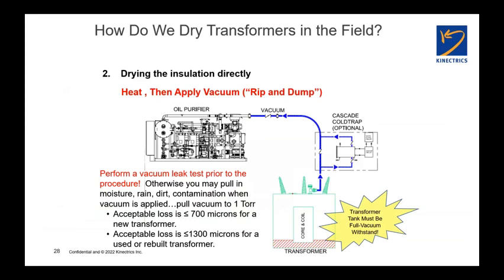Sorry, there's a variation on that theme, which I call a rip and dump. That's where you connect an oil processor, use it to push heat into the transformer, and then you very quickly pull the oil out and apply vacuum. So now you've got hot paper and vacuum. So you kind of have heat and vacuum at the same time, except we're not putting heat in while we're pulling vacuum.